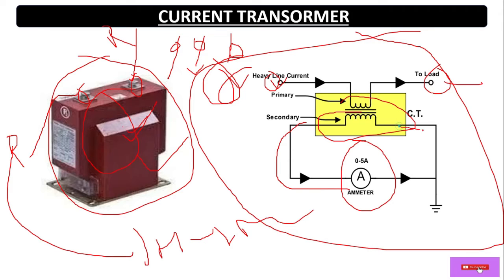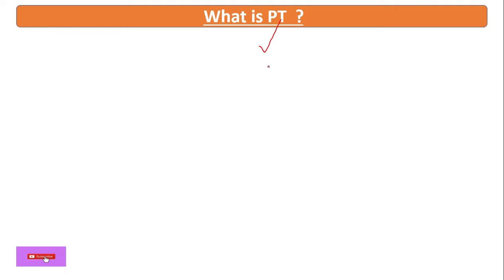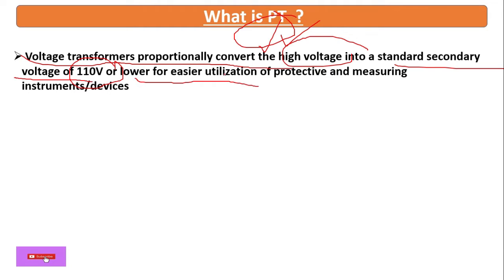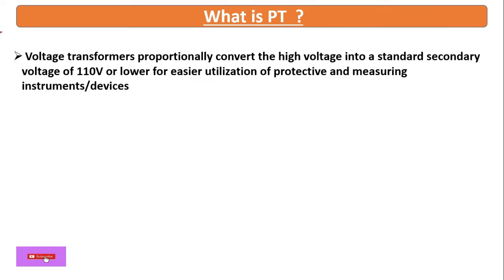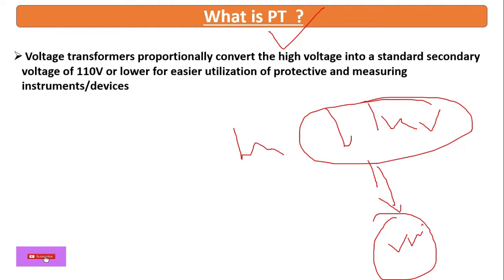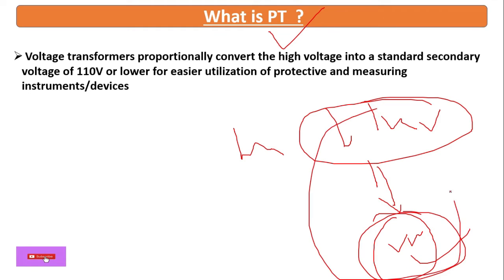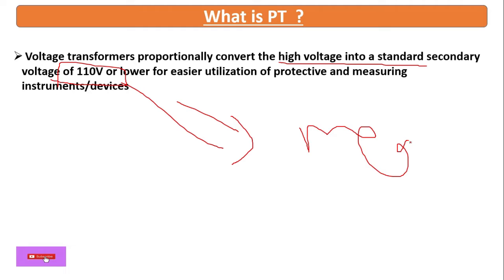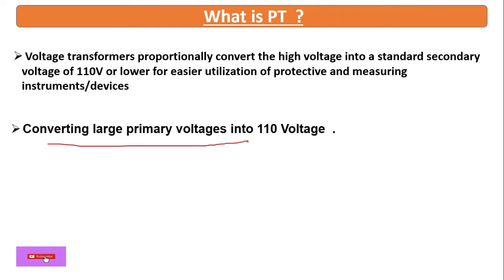Now, PT stands for Potential Transformer. It is used to measure voltage. A voltage transformer proportionally converts high voltage into a standard secondary voltage of 110 volts for easier utilization with protecting and measuring instrument devices. This is used to convert the high voltage side — if you want to measure a high voltage like 11 kV and connect it directly to a voltmeter, it will burn. That's why we use a PT to convert high voltage into 110 volts.